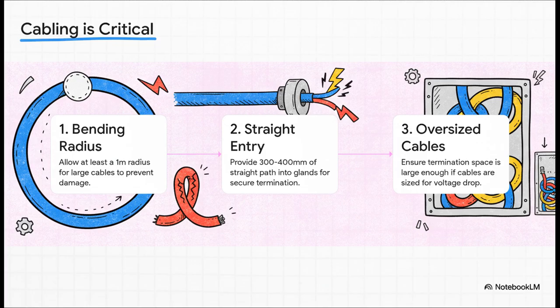You can't just assume these giant power cables will magically connect themselves. They're incredibly stiff. If you don't design in enough room for them to bend properly and go into their connections nice and straight, you're just asking for a bad termination down the road. It's a tiny detail that can literally make or break an installation.